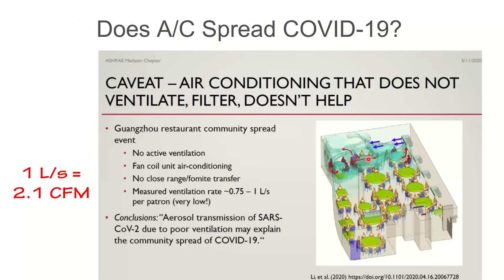So the primary reason that people spread COVID from one to another in that seating area is because they were just recirculating the same air over and over again and not bringing any new fresh air in at all to dilute it down. So yeah, I guess you could say the AC spread COVID, but the fact that the AC was done improperly is the reason why it helped spread COVID, right? Just AC itself is not the problem. And by the way, it could have easily been heating, or any ventilation or any fan-based system would have done the same thing if you weren't bringing in fresh air. So we're going to talk about fresh air specifically.